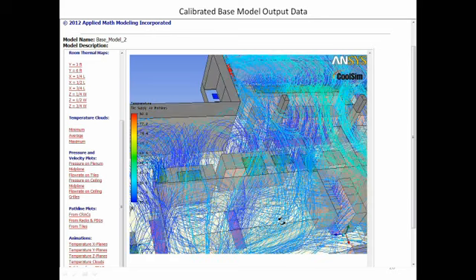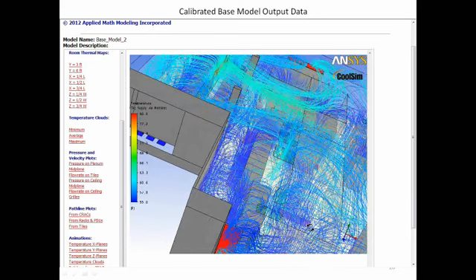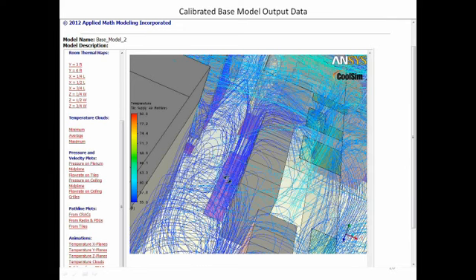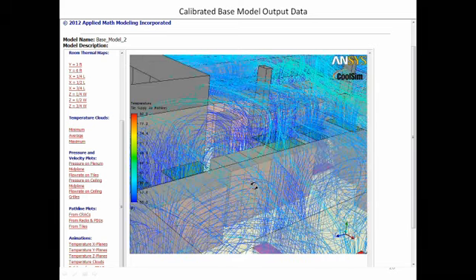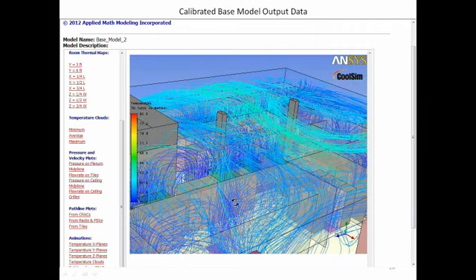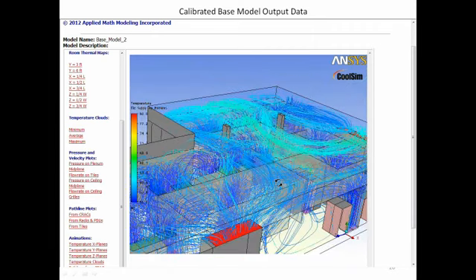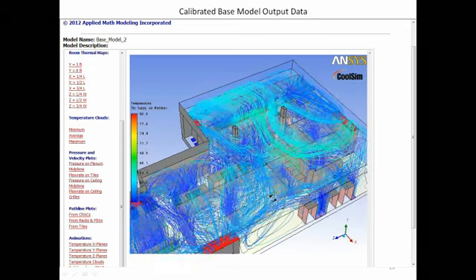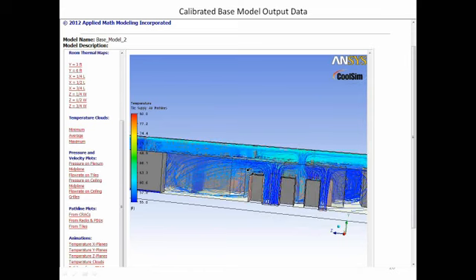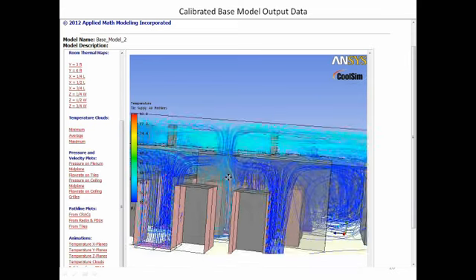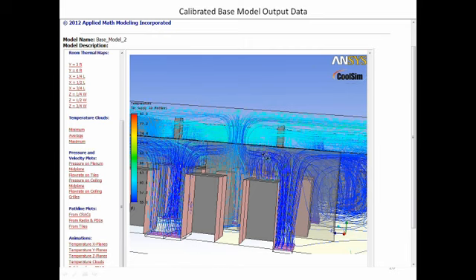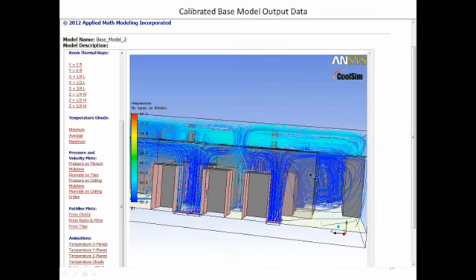The way this should work is that you should see no pathlines in the room; the air should come up out of the tiles and into the rack and stop. You should see no flow in the return ducts, because all we're showing here, Liz, is just supply, right? Exactly. It's very cold air, and it's just blowing all over the place, way over and above the racks, because there's way too much coming out of the perf tiles. Yeah, look at it blowing by right here, a good example of bypass airflow coming up, not going in the rack at all, going right back to the CRAC unit. And going back cold, as you pointed out, at 58 to 60 degrees, which means the delta Ts are very poor in the CRAC, and the whole thing is terrible.